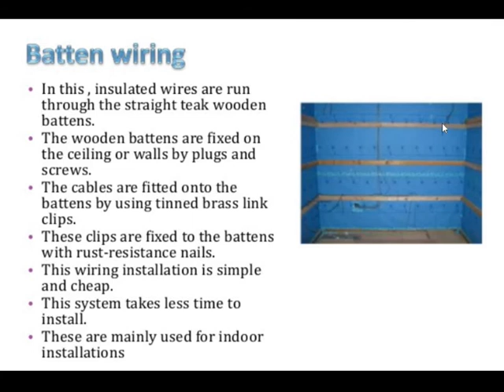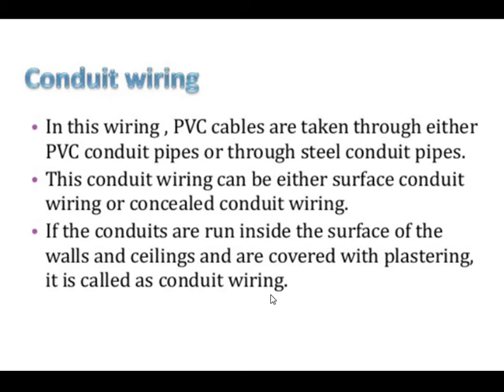Now conduit wiring. In this wiring, PVC cables are taken through either PVC conduit pipes or steel conduit pipes. This conduit wiring can be either surface conduit wiring or concealed conduit wiring. If the conduits are run inside the surface of the walls and ceilings and are covered with plastering, it is called concealed conduit wiring. Surface conduit wiring is used in industries to connect heavy motors. Concealed wiring is the most popular and common method of wiring in residential buildings. This method is the safest method of wiring and also looks beautiful.